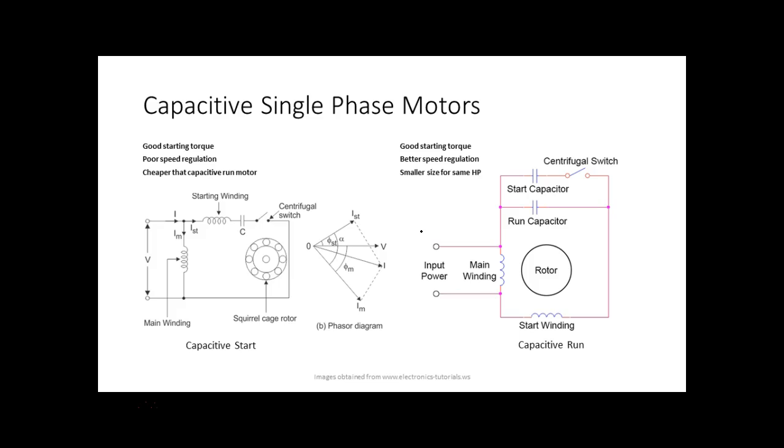Then some single phase motors have a plate on them, and you can open up the plate and look in there, and you can get to the start winding and run one. So what we do is we swap the connections. The standard way is to swap the connections on the start winding.